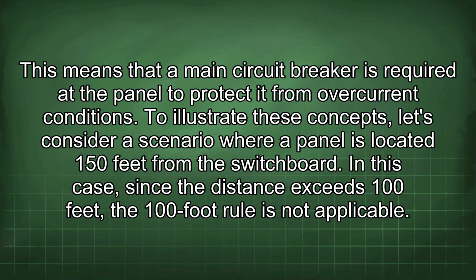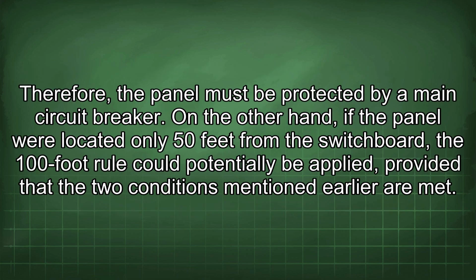overcurrent conditions. To illustrate these concepts, let's consider a scenario where a panel is located 150 feet from the switchboard. In this case, since the distance exceeds 100 feet, the 100-foot rule is not applicable. Therefore, the panel must be protected by a main circuit breaker.